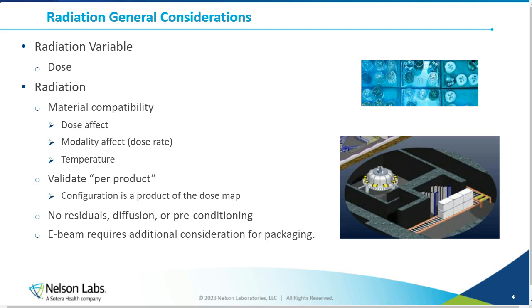For validations, we also need to consider that when we do ethylene oxide, as an example, we're validating a chamber and a cycle. With radiation, we are validating per product. So that dose is going to be based on what amount of radiation is needed to sterilize that product, not for that chamber setup, not for that cycle parameter. So with that, we're going to account for those cycles and parameters with our dose map. The other nice thing about radiation is there are no residuals, there's no diffusion as such. So whatever goes in, it's not going to be any more radioactive when it comes out.